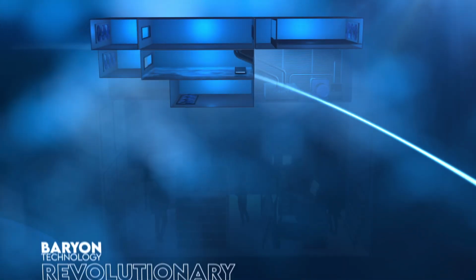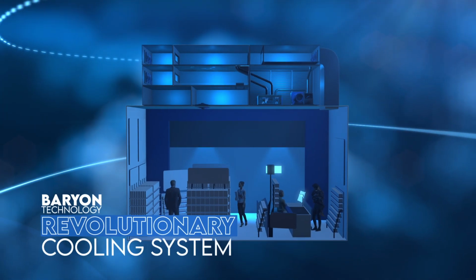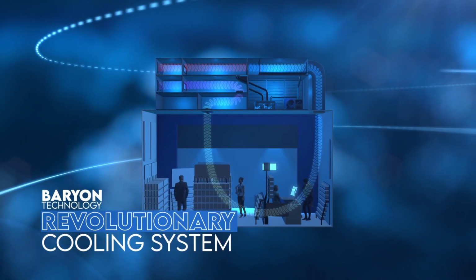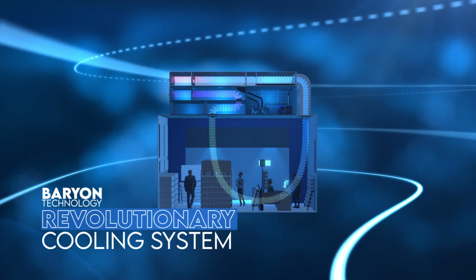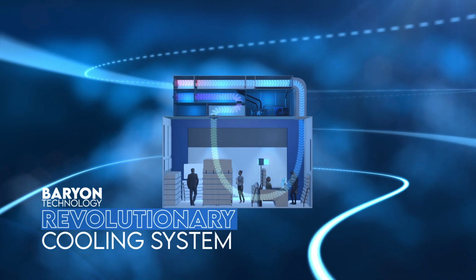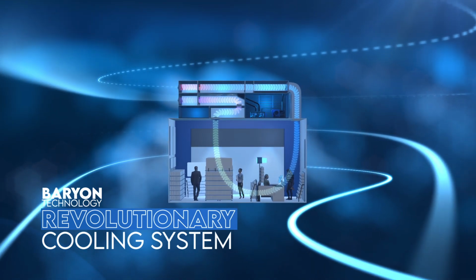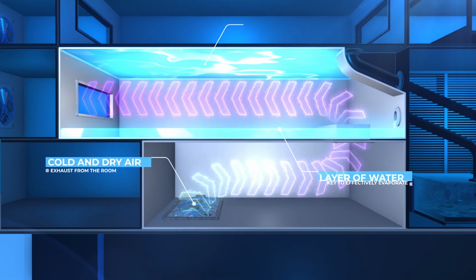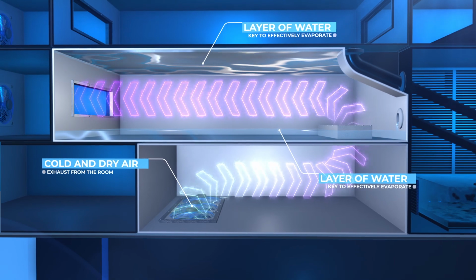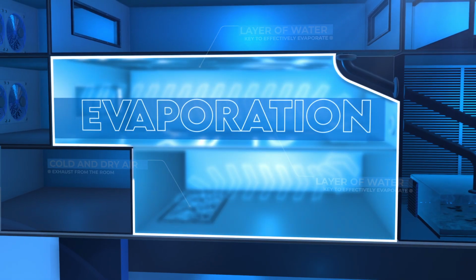The system allows us to effectively cool the air with water evaporation in a humid climate due to a unique flow arrangement. The system takes the air from the conditioned space, which is cold and dry in the summer season, and delivers it to the channels of the two-phase cooler, which are wetted with water. When cold and dry air contacts water, the water starts to evaporate very effectively, which realizes the first stage of the process.